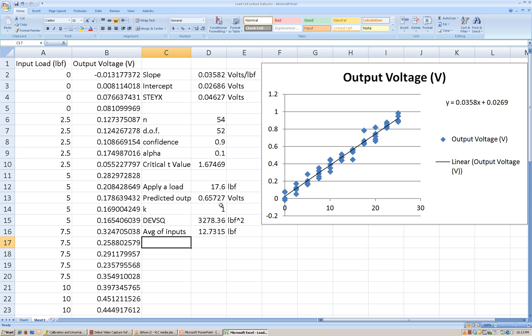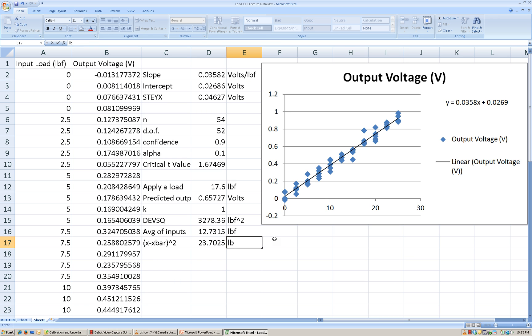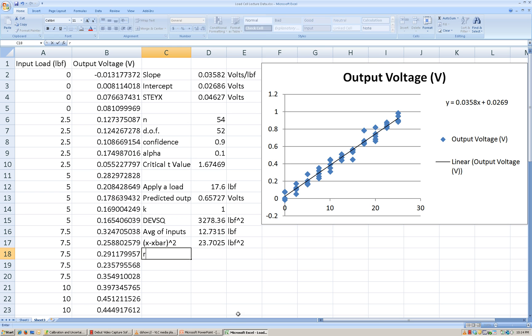I have the average of all the inputs. I need to get the value of the applied load and take the difference. This would be (X minus X-bar) squared. To come up with that value, I'm going to take the applied load, subtract from that the average of all of the loads used to come up with the calibration line, and square it. That becomes pounds-force squared as well.